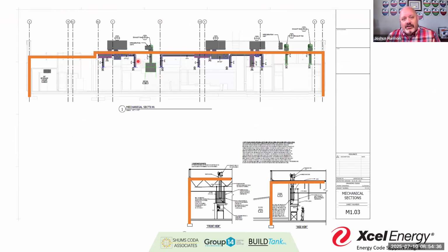They're not going to know that an ST4 looks like this, right? Or all I see is 8-inch or 12-inch line. Well, is that flex? Is that round? What is it? So that when my staff, or when I'm out there as an inspector, I'm seeing what's going on and I can evaluate whether that is right, because a lot of that mechanical design is based on equivalent lengths, and if we put the wrong elbow, we may not get the right amount of air at the end.